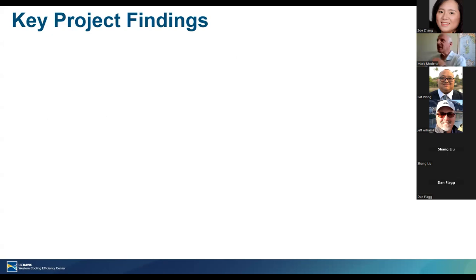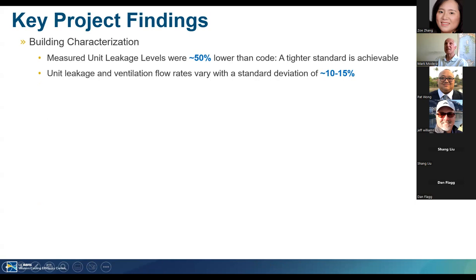I'll tell you all the key project findings right at the beginning and then spend some time backing those up. In terms of building characterization, the big takeaway was that the measured leakage levels were approximately 50% lower than code — meaning tighter — suggesting that a tighter standard is clearly achievable. Unit leakage and ventilation flow rates were fairly consistent, with a standard deviation of about 10 to 15%.